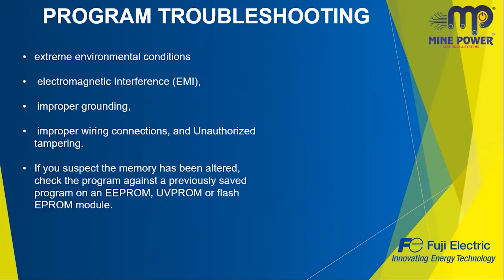First of all, it's about programming troubleshooting. Here the fault is in the programming itself, because sometimes you don't have to create the program in all conditions. Sometimes you have to get the backup of a previous program and update that. In such cases, the program may be in a fault condition. For example, if the input is an NC but the output is programmed as NO, those types of problems will occur and cause a process fault in the machine.